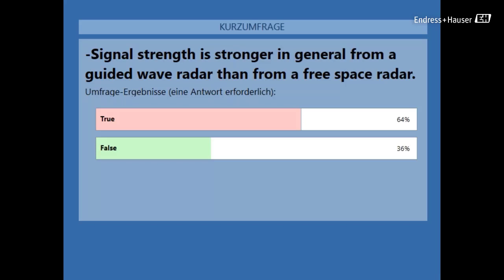One of the biggest mistakes is people take a guided wave radar, even buy a calibration certificate from the supplier, stick it into the tank, wire up the 4-20 milliamp signal, and walk away. Please don't ever do that. Always set span and zero in the tank or bypass where you mount them. That is very important for performance and accuracy.